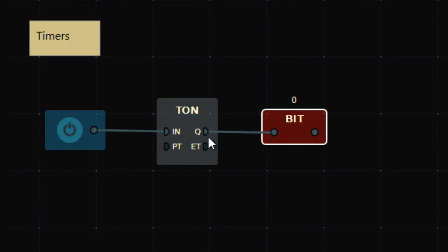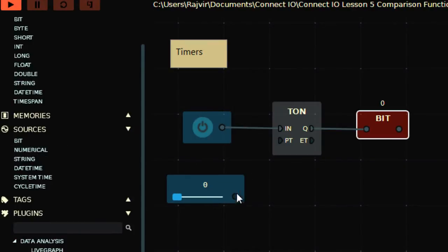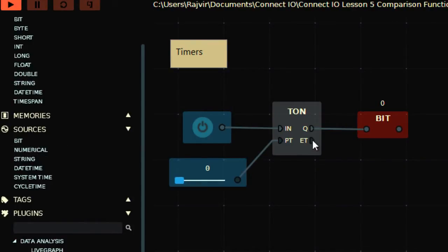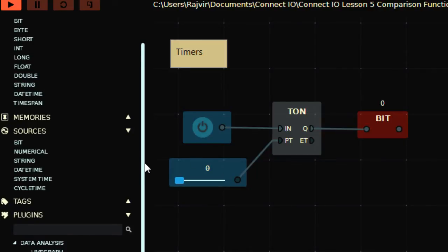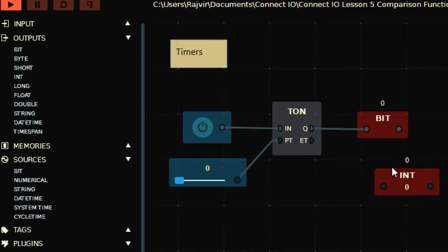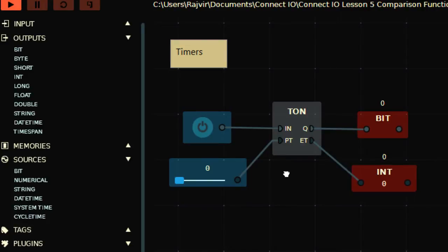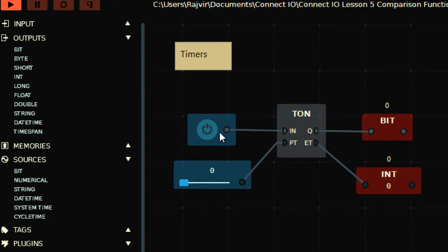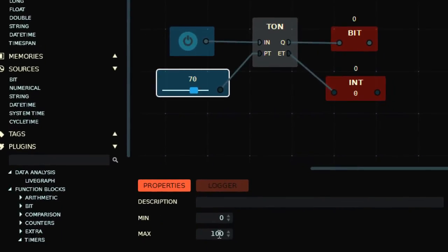To provide a delay, we need to provide the delay at the PT terminal. ET is the accumulated time, and PT is the preset time — the time after which your output will be on. IN enables the timer, Q is the output, and PT is the time delay.